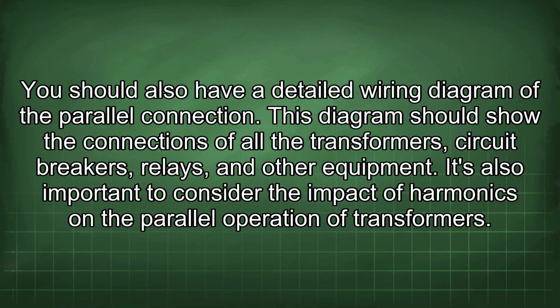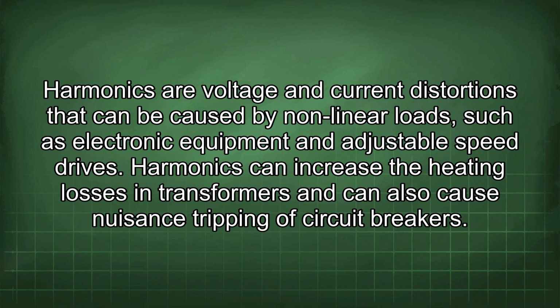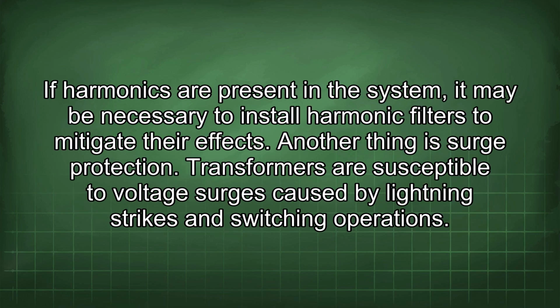It's also important to consider the impact of harmonics on the parallel operation of transformers. Harmonics are voltage and current distortions that can be caused by nonlinear loads such as electronic equipment and adjustable speed drives. Harmonics can increase the heating losses in transformers and can also cause nuisance tripping of circuit breakers. If harmonics are present in the system, it may be necessary to install harmonic filters to mitigate their effects.